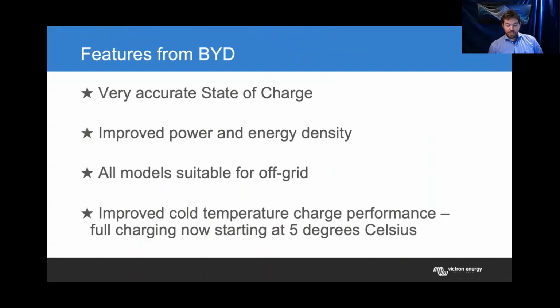So some of the good features, some of the improvements I should say that have been made. Very accurate state of charge. So this was a concern that we had with some of the earlier models from BYD. This is now very, very accurate. There's no low power fade. Basically where the current is low, the system would detect it and adjust the state of charge accordingly. That being said, like all state of charge monitoring, it will fade out over time. It's not perfect. There's losses through the inverter charger, through heat and noise and inefficiencies, sound.